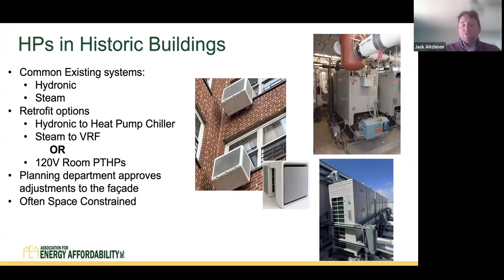Another option for a steam system is the 120 volt room package thermal heat pumps. When I say 120 volt, this really means that we can plug them in a general outlet. Now, in some cases and in some jurisdictions, even though that outlet has enough electrical capacity for that packaged terminal heat pump, you still may need to run a dedicated circuit because it's considered the permanent heat source. But it is a great option. It significantly reduces the need for electrical upgrades. And one of the big considerations around these package thermal heat pumps is, like any heat pump, it needs access to the outside air. So you may be making facade alterations, and that is something that needs to be coordinated with the planning department. Lastly, in our historic buildings, we often have a lot of space constraints. Space is at a premium, and so that's another big consideration we need to make while electrifying those older buildings. Next slide, please.